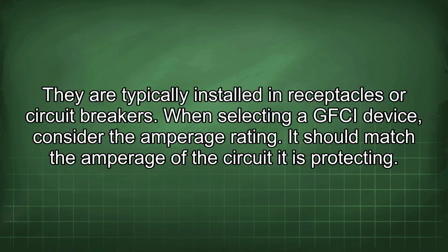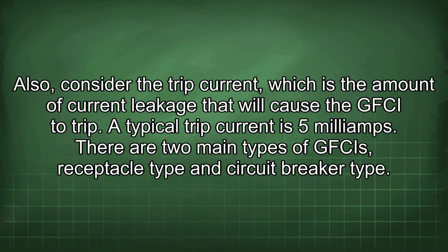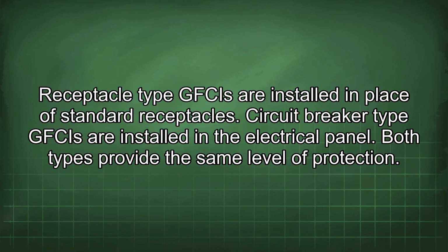When selecting a GFCI device, consider the amperage rating. It should match the amperage of the circuit it is protecting. Also, consider the trip current, which is the amount of current leakage that will cause the GFCI to trip. A typical trip current is 5 milliamps. There are two main types of GFCIs, receptacle type and circuit breaker type. Receptacle type GFCIs are installed in place of standard receptacles. Circuit breaker type GFCIs are installed in the electrical panel. Both types provide the same level of protection.